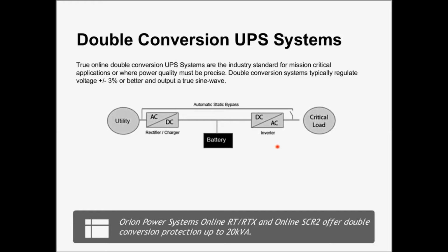The voltage regulation is plus or minus 3% or better. And one other thing this design has is an automatic bypass switch. So if any of these components fail, it automatically routes power around the internal components and powers the load. So there's a lot of really neat things that it can do. Just to give you a quick example, the voltage regulation on this unit is plus or minus 3%. The line interactives and standbys are plus or minus 10 to 15%, so it's a pretty big difference. One other quick thing is, since the battery is wired in parallel, there's no transfer time when the power goes out. It's a seamless transition from being powered from the rectifier charger to the battery because they're wired in parallel.